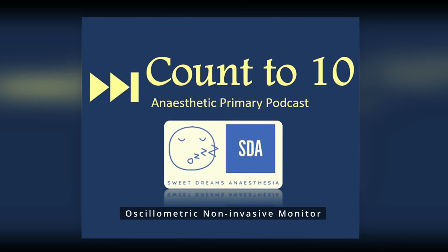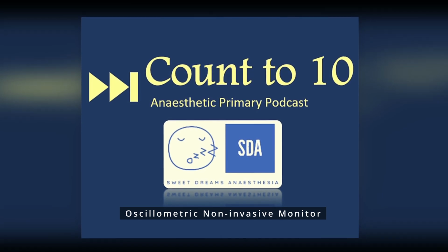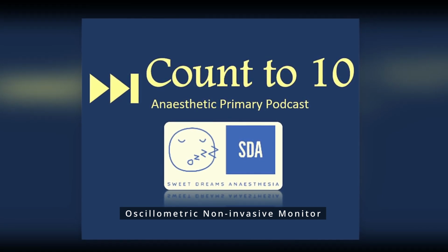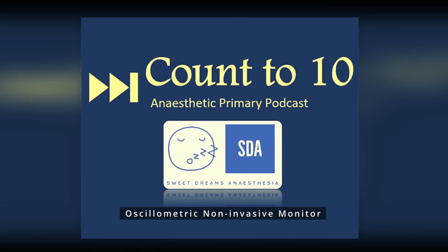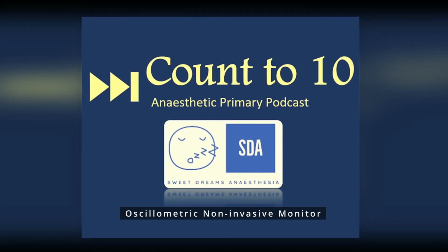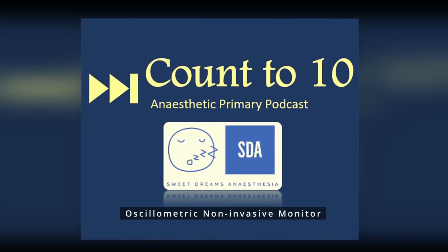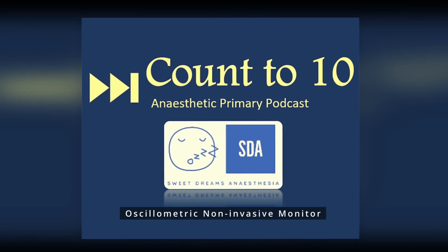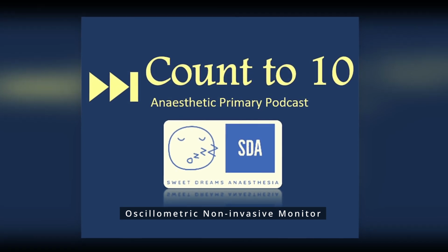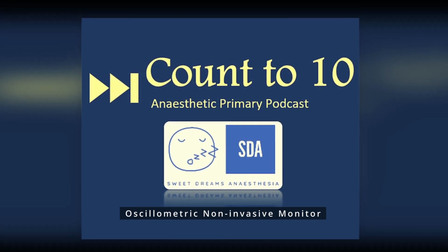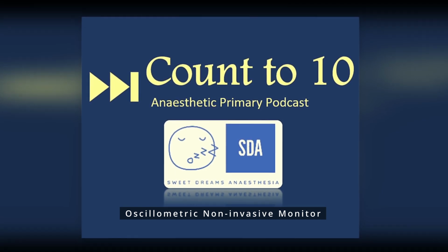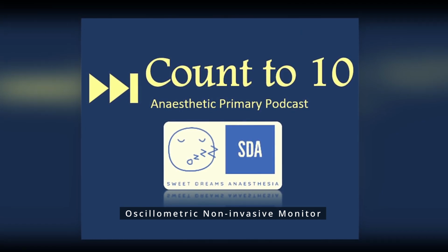The way this is done is that a unique graph is made which depicts on the x-axis time and on the y-axis the amplitude of the oscillations. This graph is superimposed with a graph of cuff pressure, and then these two graphs are used to give us our outputs. So the setup for an automatic oscillometric non-invasive blood pressure is the same as what you do for an auscultation blood pressure.